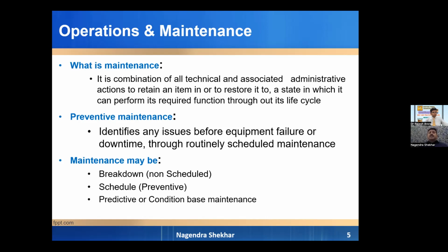Maintenance is basically of three kinds. One is preventive maintenance, which is scheduled maintenance. So you have a schedule that after a certain period you will do this or that. It may be that after 10 earth fault trippings, or 18 earth fault trippings, you have to change the oil of OCBs. In the previous versions; nowadays we are using SF6 and VCBs. Or changing our silica gel and breather after a certain time, that may be yearly, six monthly, half yearly, hourly schedule. It depends.